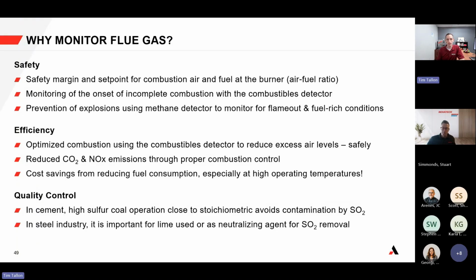That's the safety side. On the efficiency side, the concept of optimized combustion is key. How do you find that sweet spot where you don't have too much excess air, and also where you don't have enough? A combustible detector allows you to find that sweet spot to reduce excess air levels safely. By reducing excess air levels, you also reduce your carbon dioxide and NOx emissions, and you get a cost savings by reducing fuel use. So more efficiency means less excess air at the burner, which means fewer emissions and a reduction in fuel consumption.